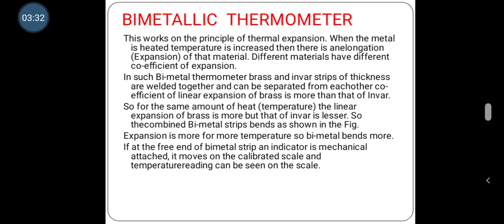Now the disadvantages. It is suitable for local mounting only. Types are available only in indicating and non-recording form. If handled roughly, the calibration may change. In comparison with a glass stem thermometer, the accuracy is somewhat lesser. Now the use: it is popular in offices, hospitals, public places and even at home. The bimetal strip can also be used in the helix shape.